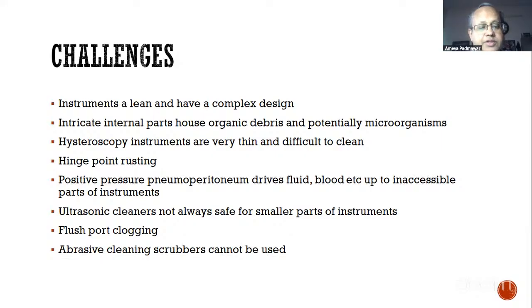They have a flushing port through which you have to inject water or saline to get rid of all the proteinaceous material. And most important, you cannot use scrubbers on these instruments as you use on open surgery instruments. If you have seen your technical team clean the instruments after you have finished with the surgery, they use a standard scrubber which is used for cleaning utensils.